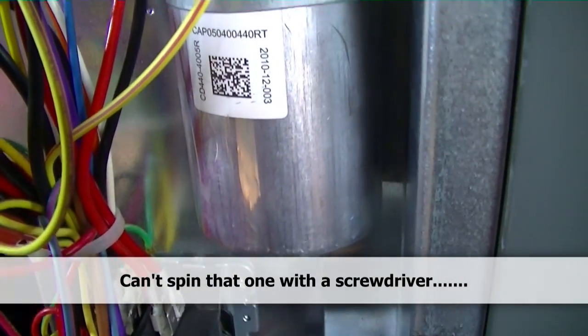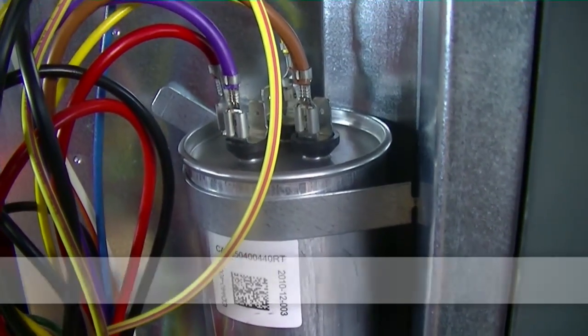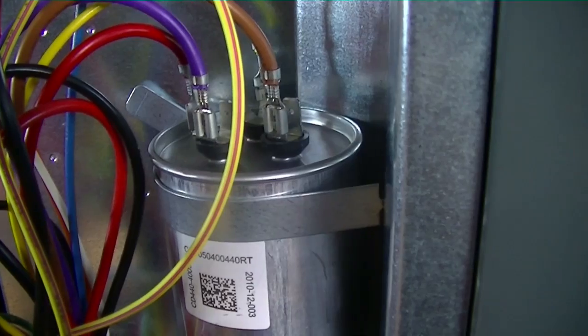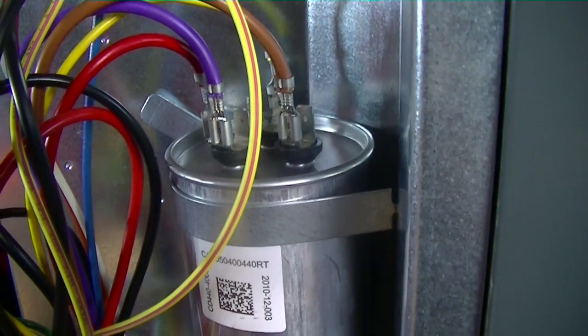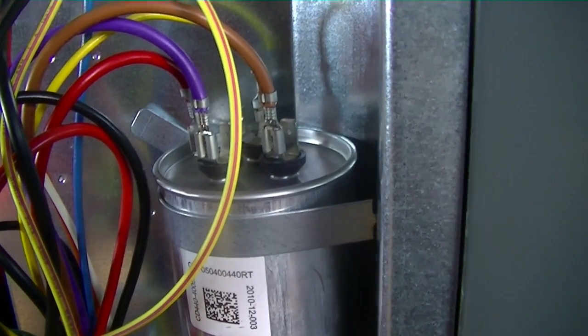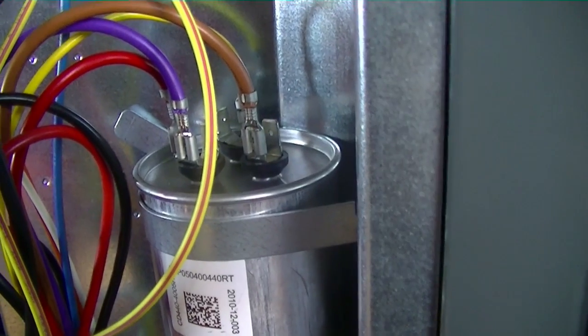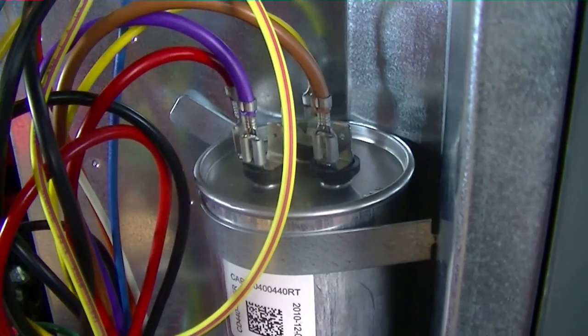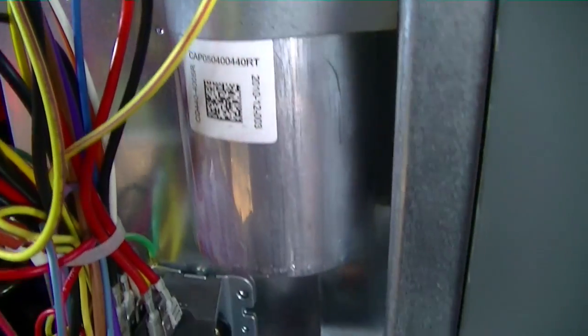So you always have to test your capacitors. Preventive maintenance is very important. Once they get to the tolerance, which is typically, I've seen them range from 3% all the way up to 10% for AMRAD I think. When you're out of the tolerance, change it. No question about it. If they say it's going bad, it's going bad. You don't want to be responsible for the thing starting the week after you work on it.